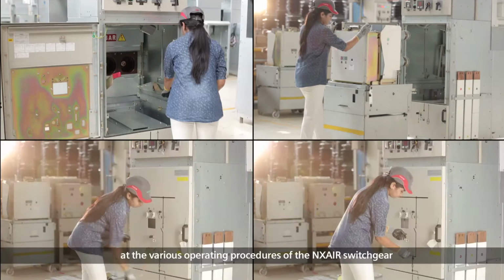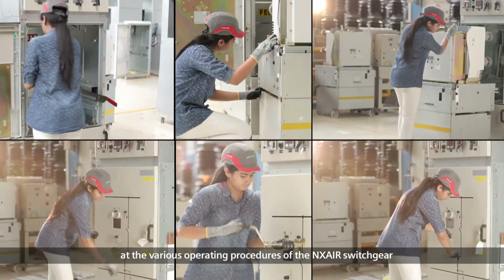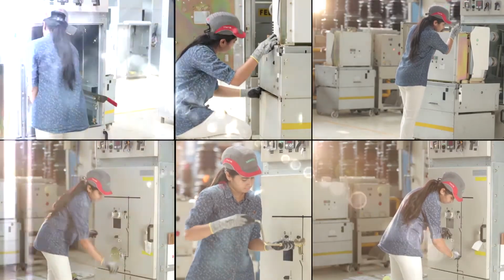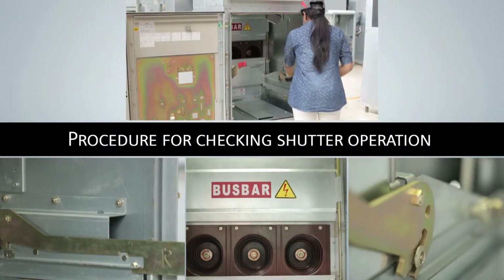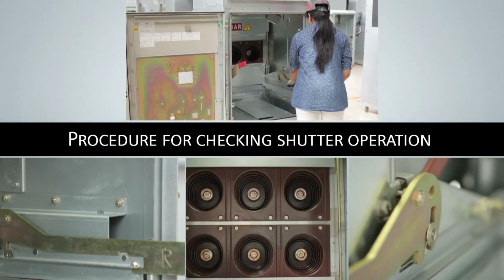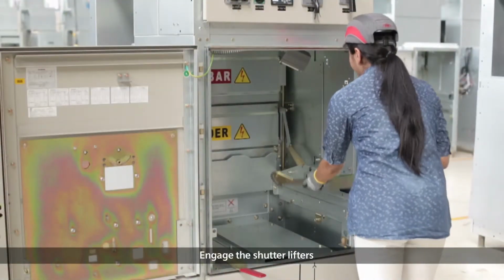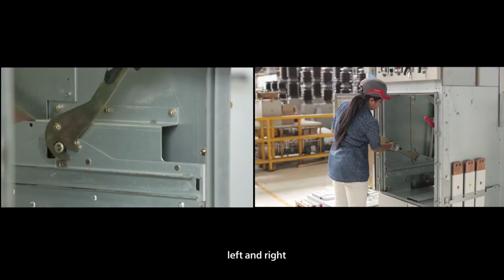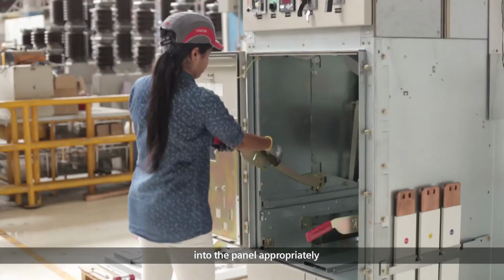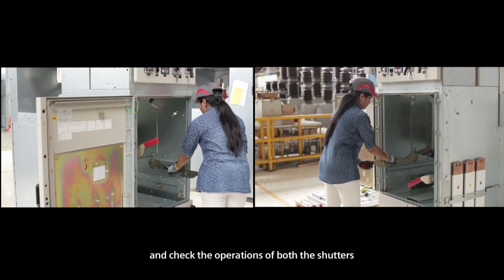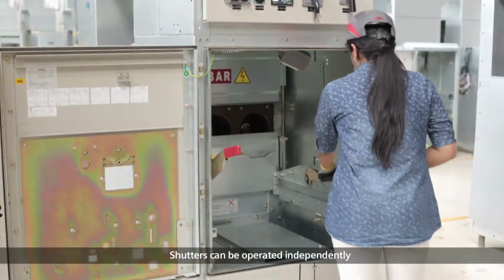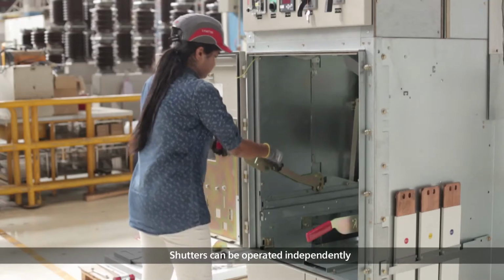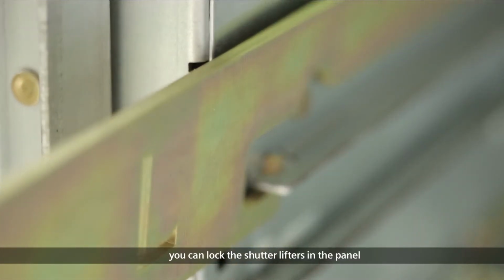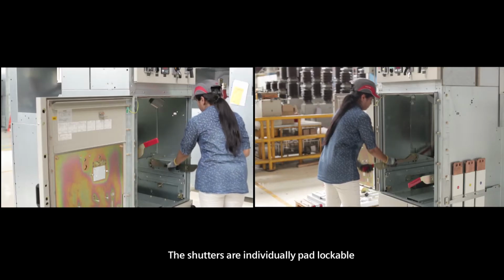Let us take a look at the various operating procedures of the NX Air switchgear. Procedure for checking shutters operation in the panel. Engage the shutter lifters, left and right, into the panel appropriately and check the operations of both the shutters. Shutters can be operated independently. You can lock the shutter lifters in the panel. The shutters are individually padlockable.